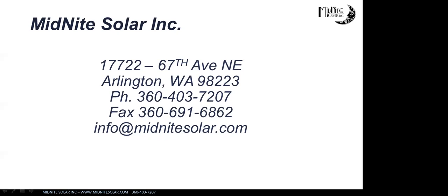One thing we recommend, for example, is setting your equalize charge voltage to the same value as your absorb voltage. That way, if somebody accidentally triggers an equalize — which you shouldn't do on a lithium battery — it would just essentially perform another absorb charge. There are a few things we recommend for lithiums as extra safety measures, like not using the temperature sensor since you won't be doing temperature compensated charging. So it's always worth calling our tech support to chat and see what additional recommendations they have.